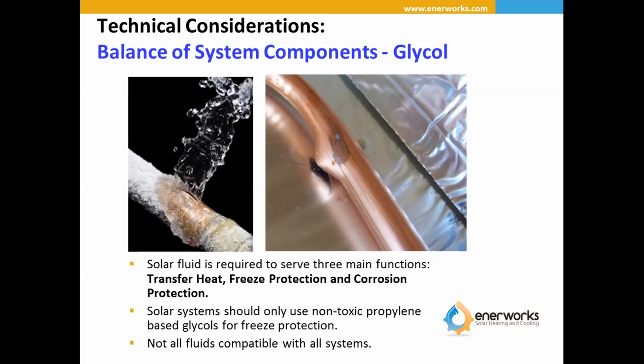And so it does two things. It provides your freeze protection, but it also provides the corrosion protection in a system. And it's really, really important that you don't use just any heat transfer fluid, because a lot of heat transfer fluids that are designed for building heating systems are nowhere near capable of maintaining the temperature swings that you're going to see in a solar hot water system. Add to that, with the steam back stagnation system, that separation of the water and the fluid from your inhibitors will often allow those to precipitate out on the pipes, and it'll actually coat them and reduce your overall efficiency.